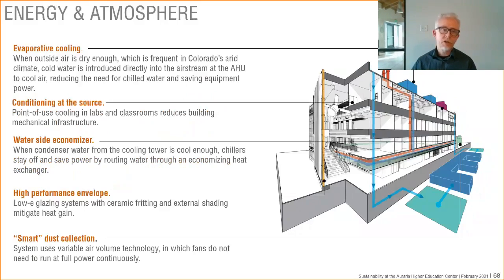Energy reduction involves optimizing a whole series of building systems. One example is conditioning at the source. This is a cooling-dominated building because the lab equipment gives off so much heat. Rather than using air to move cool energy throughout the building, we use chilled water, which is much more efficient. We move chilled water to the labs, where fan coil units blow air across it, delivering cooling right where it's needed most — a surgical way of delivering cool air where needed.